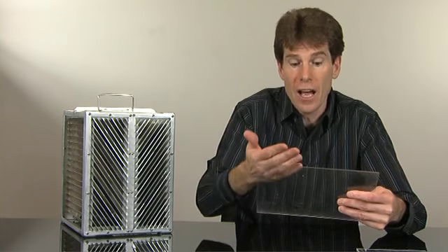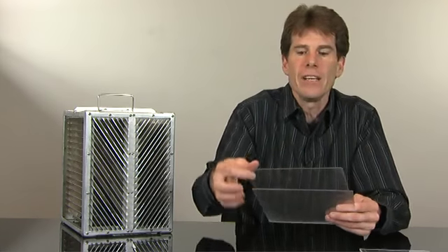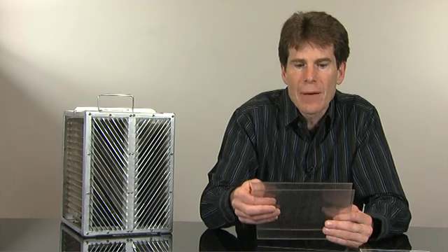If you have a downflow design where your flow is coming in, down, and out, solids do process, but the oils fight against the flow, creating issues, especially when you have very tight plate gaps. When you get in that tight plate gap position, you get fouling due to an upflow or a downflow design.